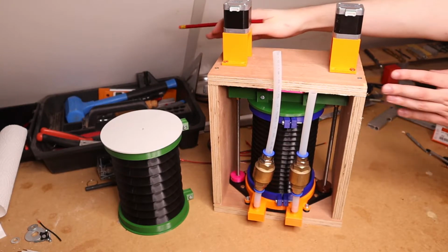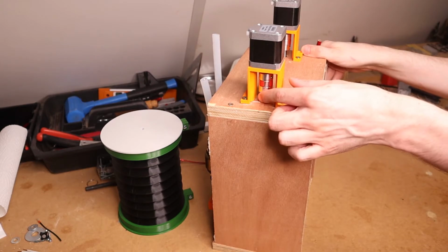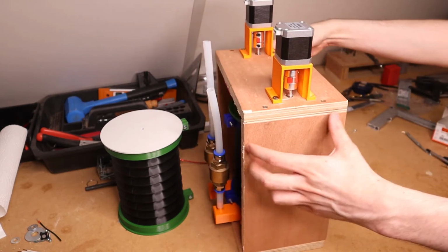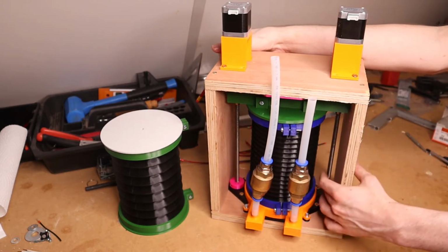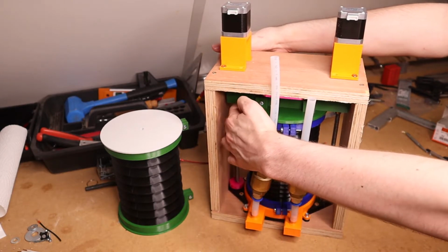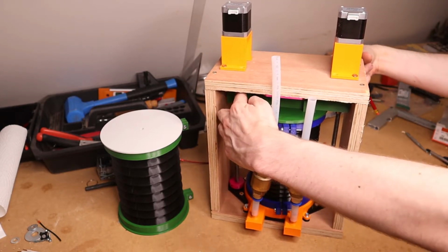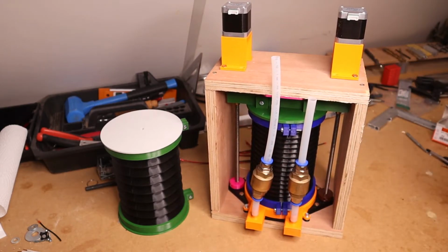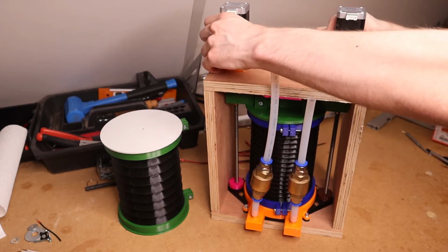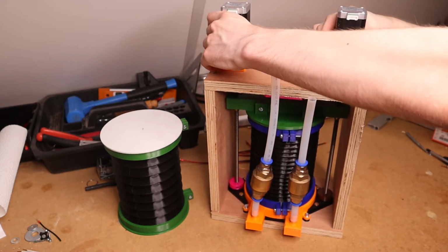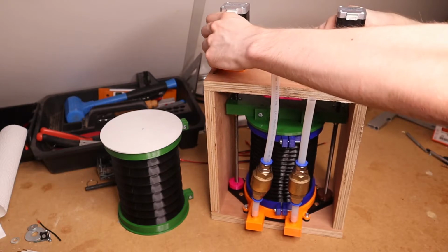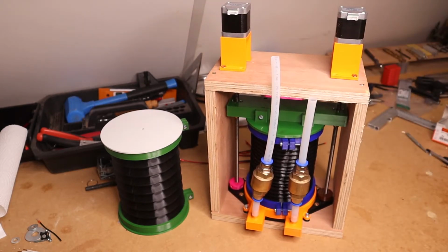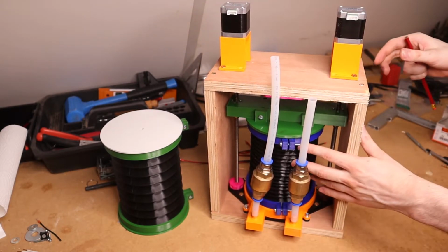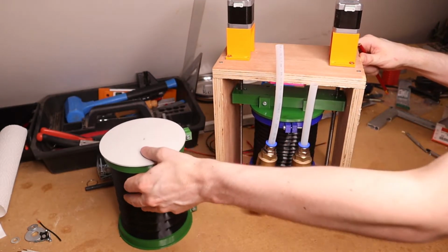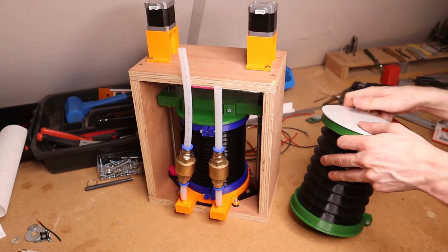So here's the pump module lifted out of the machine, and the way this works is you have two stepper motors, and then using these semi-rigid couplers, they drive these TR 8x8 lead screws, and then using the nuts here on this little cross member, it moves the bellows up and down essentially. So again, if you rotate on the couplers here, the thing moves.